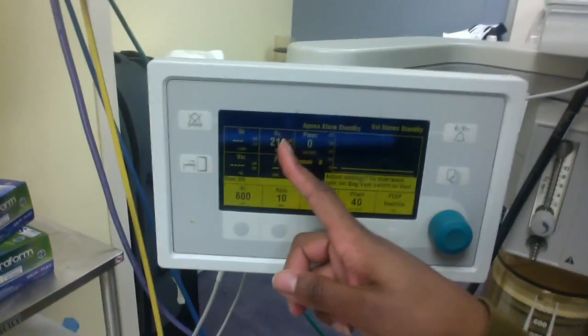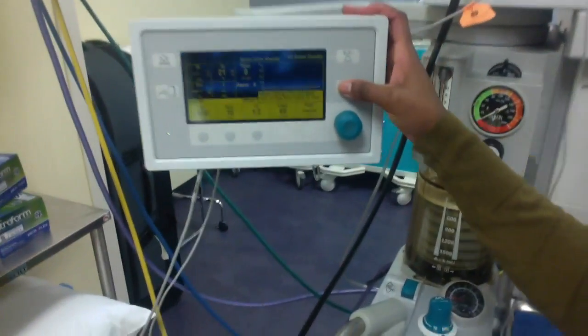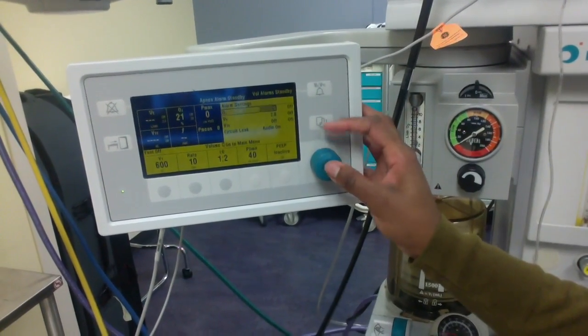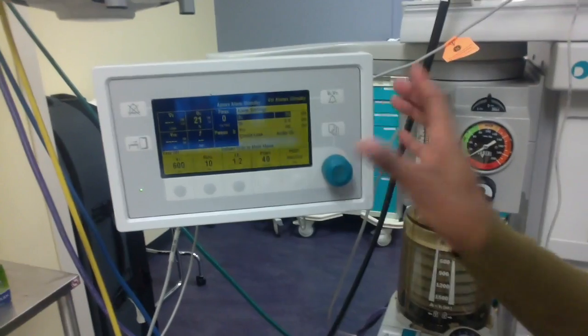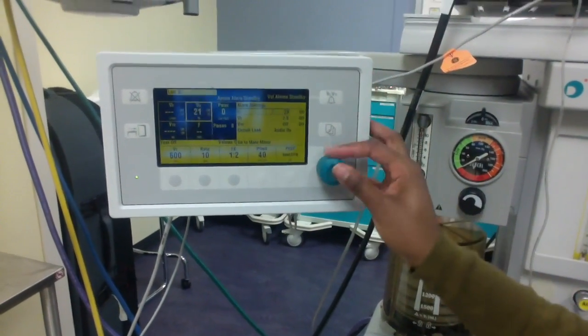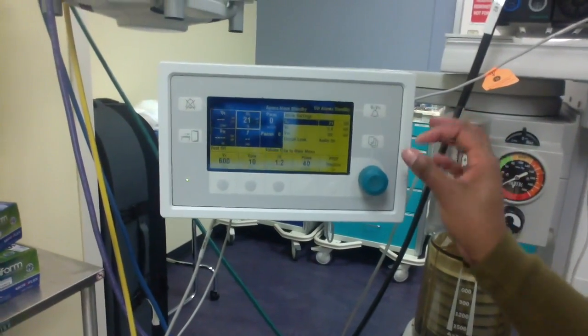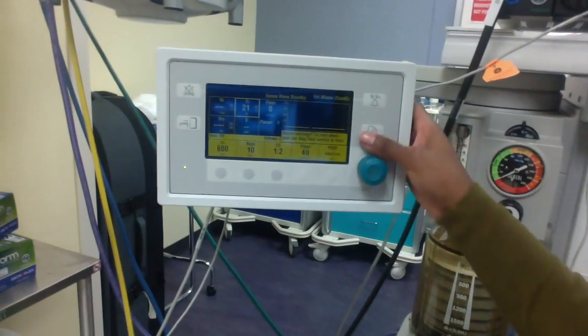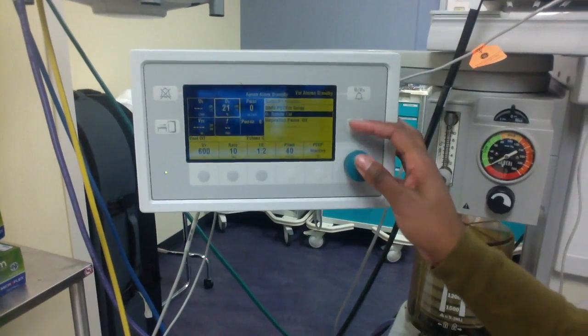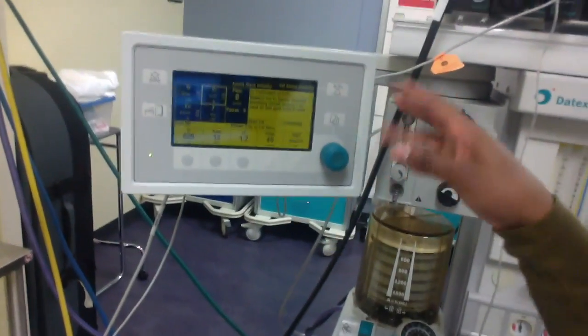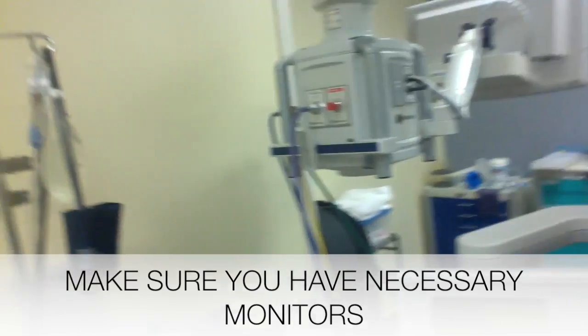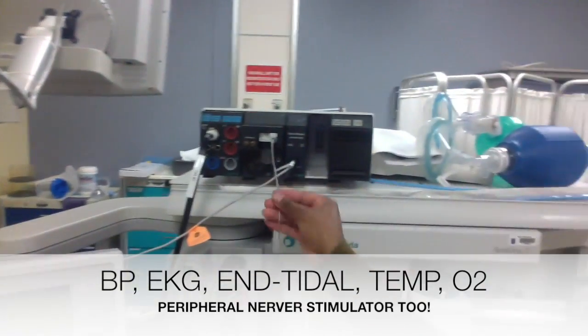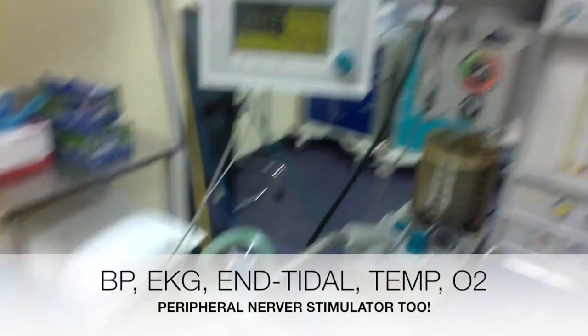So now that I've calibrated the cap to room air, 21%, what I like to do first is check my alarm, my low O2 setting. So I'll set it to something higher than 21 so that it will read that this is a low O2 alarm. And then I go back down. And now that it's at 21, I can also calibrate it. So I'm just calibrating the system, and I'll start that. This takes a few moments. While I'm waiting, I'll check around my OR here and make sure I have all my monitors: a blood pressure monitor, an EKG, an end tidal, which is this, and it's connecting here to the circuit, a temperature probe, and an O2 sat probe. And if I need one, a peripheral nerve stimulator.